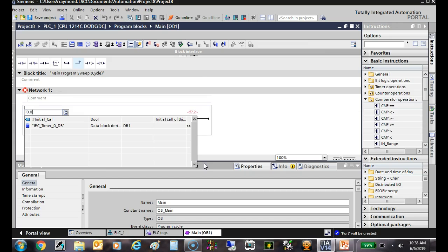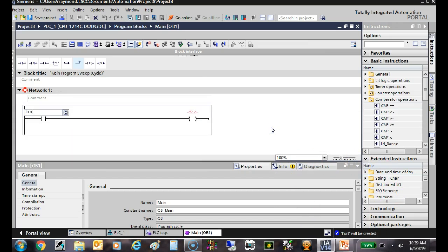Allen Bradley, when we use the dot, we specify a word. What we do on this one is I'll give y'all a list. If I wanted to specify a whole byte of inputs, I would use IB, which is pretty straightforward, right? If I wanted to specify a whole word, I would use IW, right? And that's the same thing true on outputs. So we'd start off with input 0, right? Then dot 0. Now, when you get past the number of inputs, remember your extra module is out at word 8.